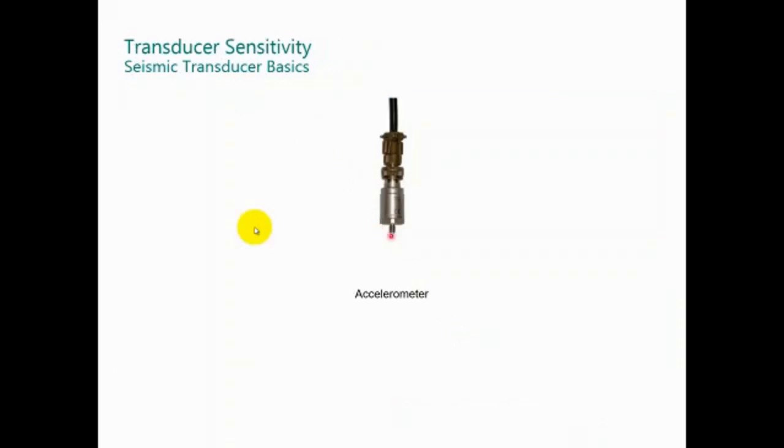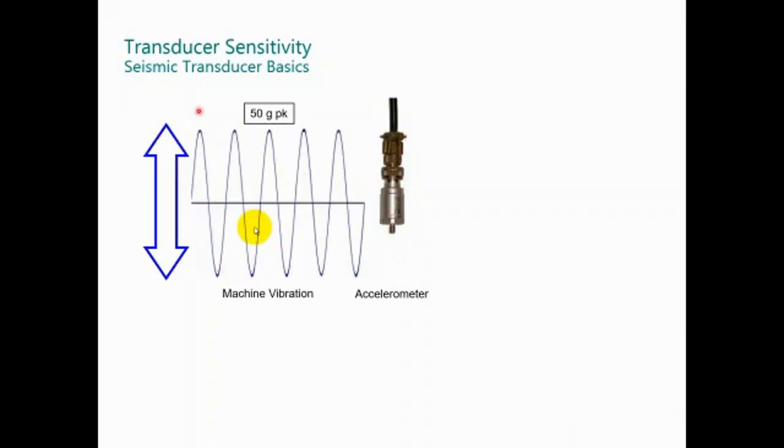First is the need to define the sensitive axis. Every transducer has a sensitive axis where they convert the vibration into electrical signal. This electrical signal must be proportional to the vibration. In this case, 50 g's peak is equal to 5 volts peak to peak.